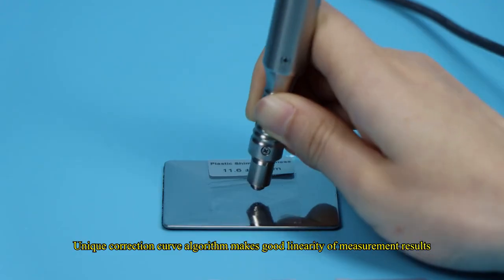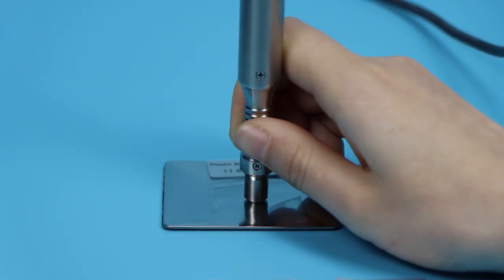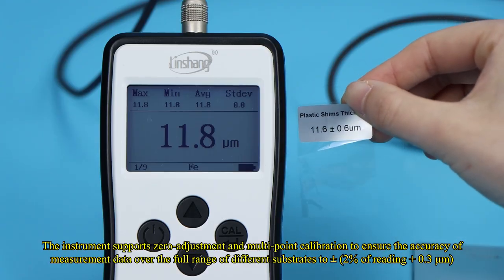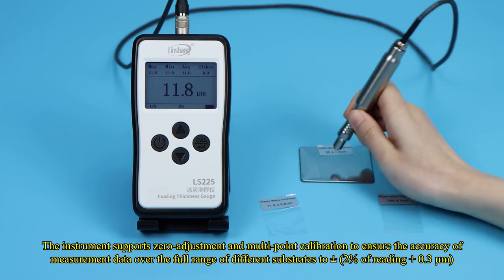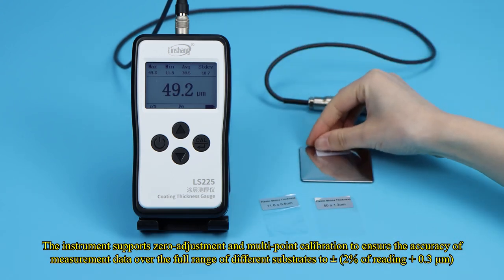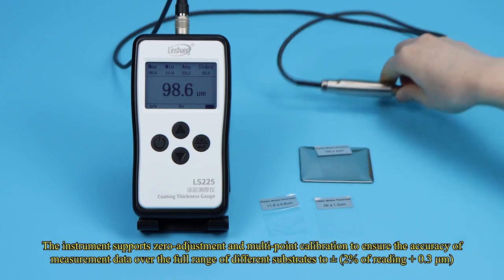The instrument supports zero adjustment and multipoint calibration to ensure the accuracy of measurement data over the full range of different substrates to plus or minus 2% of reading plus 0.3 micrometers.